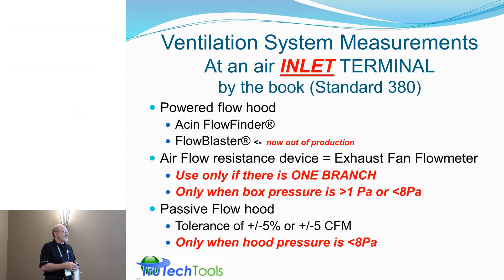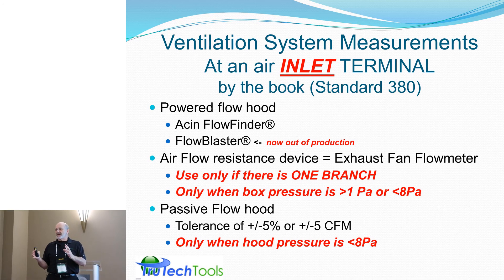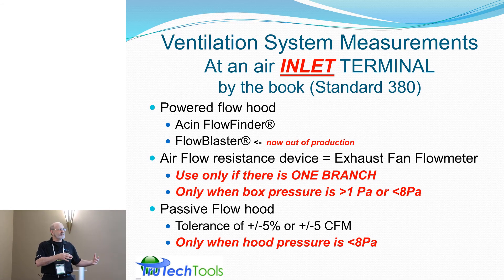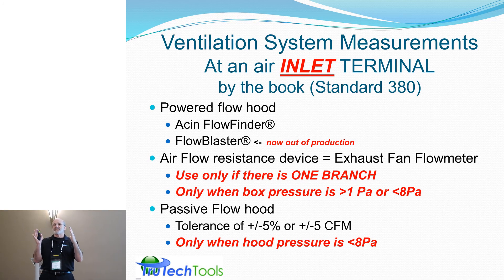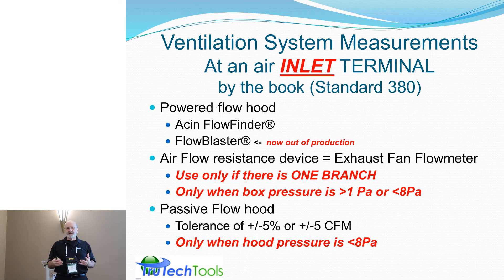The airflow resistance device is this exhaust fan flow meter, and there are limitations on it. You can only use it if there's one branch because of interaction — system effect. When you put this device on, it could affect airflow out another part of the system. The box pressure has to be within a certain small range; beyond that range, it starts to interact with the system and is no longer a good measurement. It starts to be fuzzy because air is compressible — air is squishy.